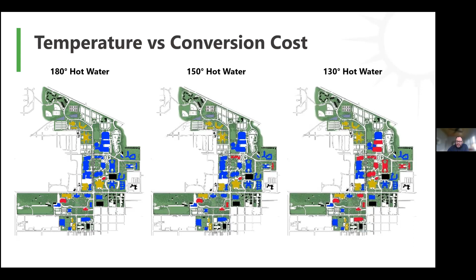At 150 degrees, a few more buildings show up, and at 130 degrees we saw a significant number of buildings needing substantial work—modifying terminal units and revising HVAC systems. That's why 150 degree hot water temperature was selected, to minimize money spent on the building side and maximize the effectiveness of the central plant systems.